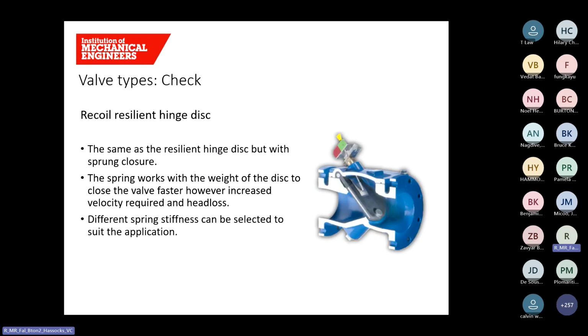A variation of the resilient hinge disc valve is the recoil version, and in this valve, as well as the disc closing on gravity, it's assisted by a spring which closes the valve faster. But this valve does require higher velocities to keep the valve open. There are options for installing different spring stiffnesses to suit the application.